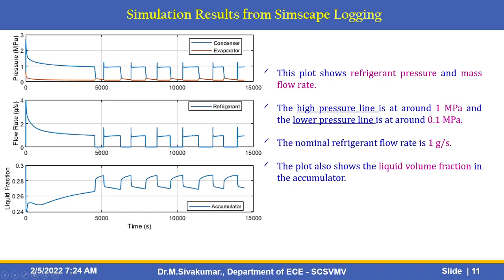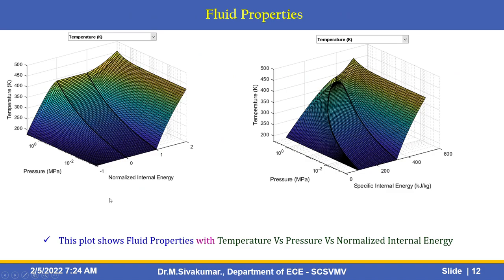This plot shows refrigerant pressure and mass flow rate. The high pressure line is around 1 MPa and the low pressure line is around 0.1 MPa. The nominal refrigerant flow rate is 1 gram per second. This plot also shows the liquid volume fraction in the accumulator.